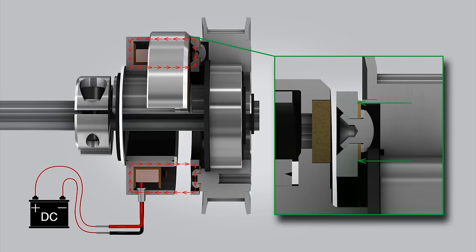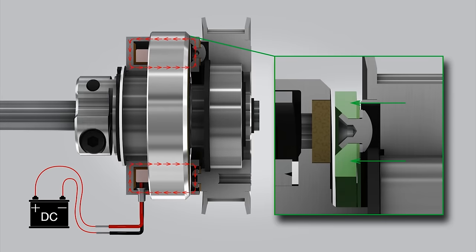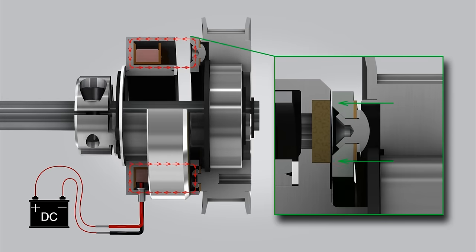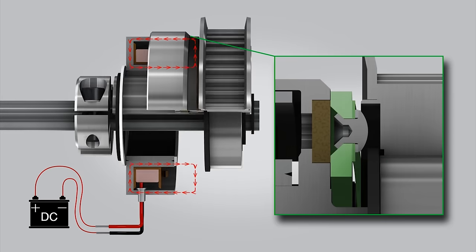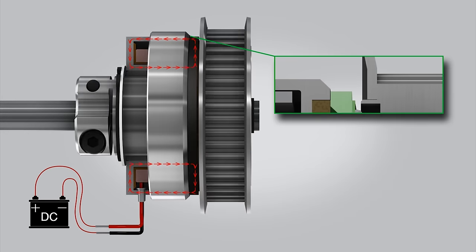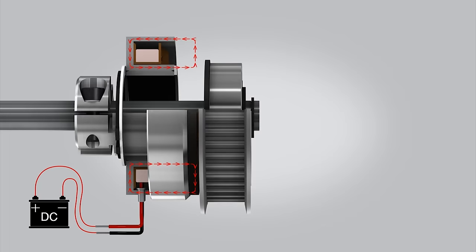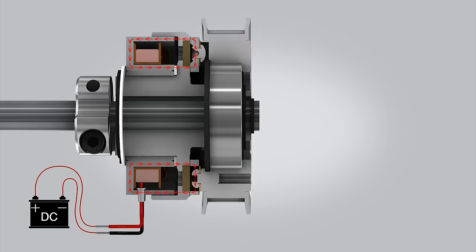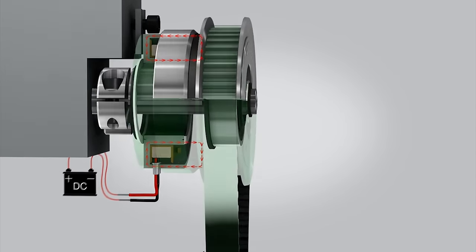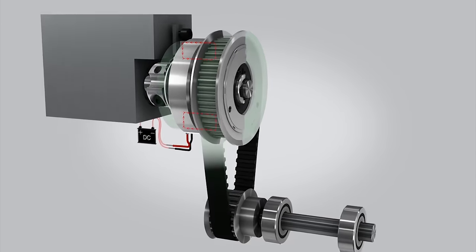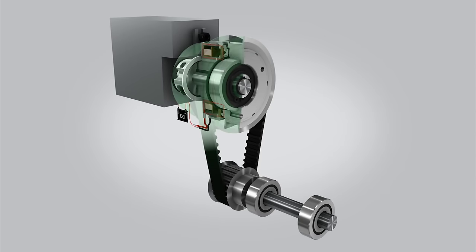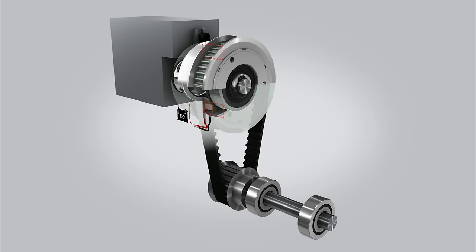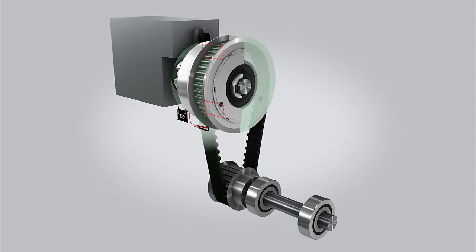The force is large enough to deflect the flat spring and the armature is pulled across a small air gap into the rotor face. The friction between the rotor and armature allow the driving shaft and armature to rotate at the same speed.